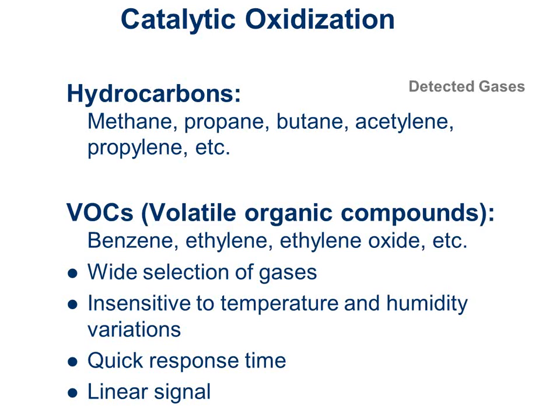You can use it for a pretty wide range of gases, so it's available in many different types for many different types of gases. And it's pretty good about ignoring the effects of temperature and humidity in regards to its gas sensing ability. The sensors respond quickly, and they're pretty much a linear signal. If I have this breakdown, I can tell you it's this many parts per million, and it follows a nice straight line without any weird curves.